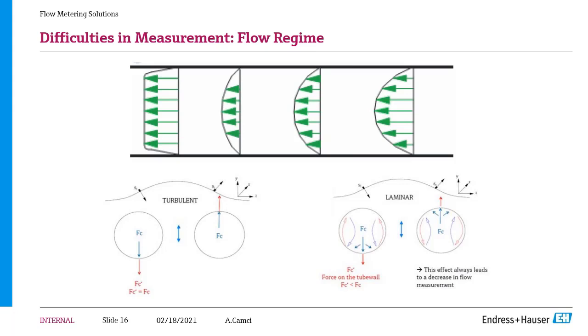the liquid will tend to have a laminar flow, which is shown on the right-hand side of the screen. Therefore, you can see the flow is mostly focused on the center line of the pipe, and there are some swirling effects on the pipe walls. Then the Coriolis force that should be created by the liquid is sensed less on the outer tube, and this will lead to a decrease in flow measurement.